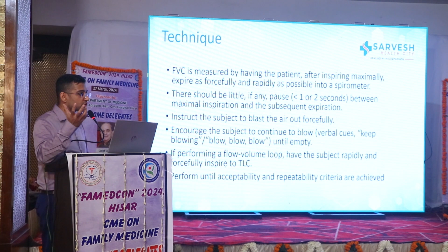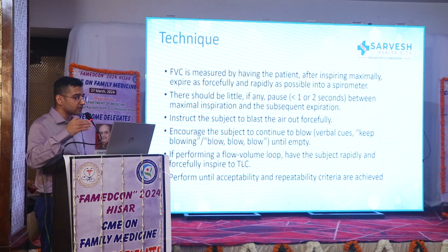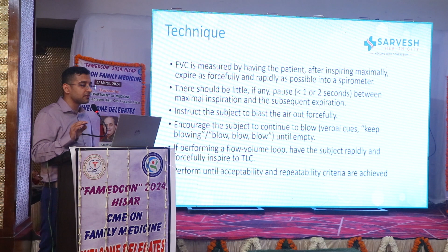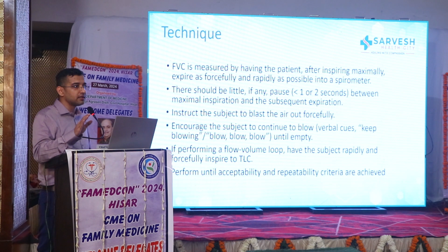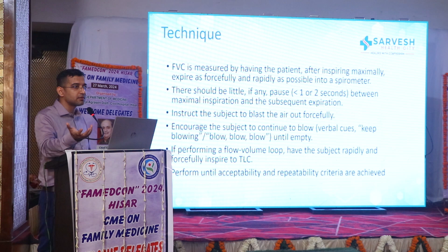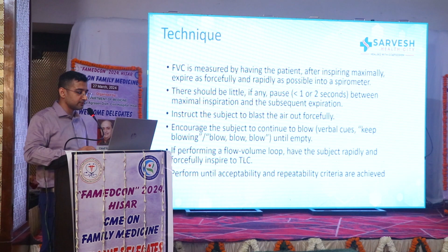Usually the machine will prompt when to stop expiring, or if the patient is continuing to expire, it should continue to at least 15 seconds according to the current guidelines. 15 seconds, or until the machine detects that the flow has decreased, and it will automatically prompt the patient to stop the expiration. And after stopping the expiration, the patient should perform an inspiration to calculate FVC.